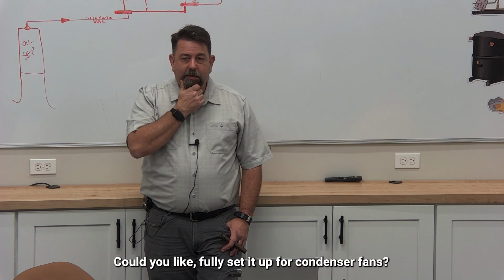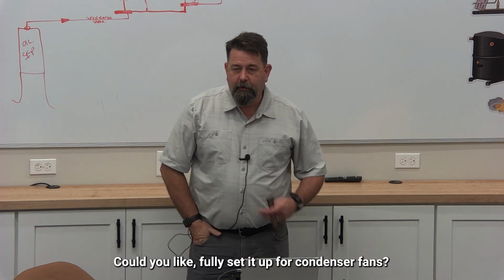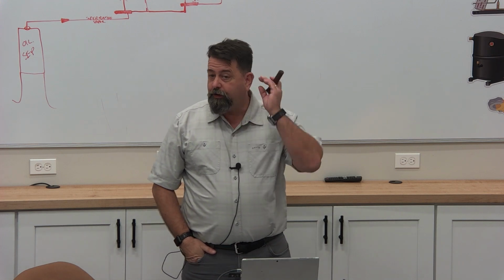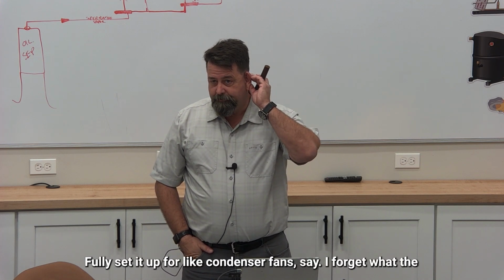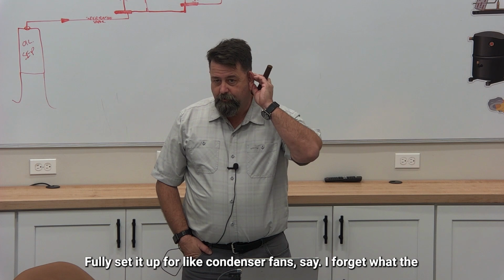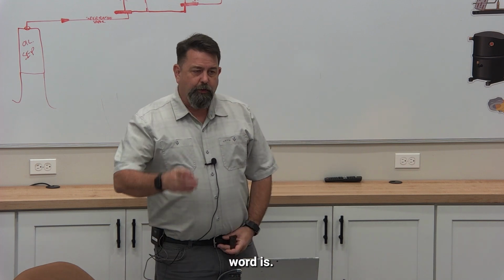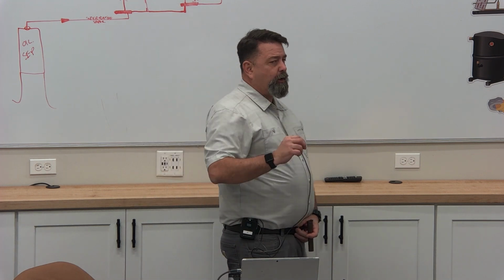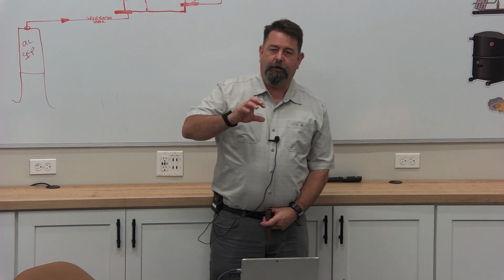Could you fully set it up for condenser fans? What would that board be called? I forget what board - your condenser fans are using just a 0 to 10 volt signal, they're not bipolar. That would be a bipolar motor stepper, used for any electronic valve that's bipolar.